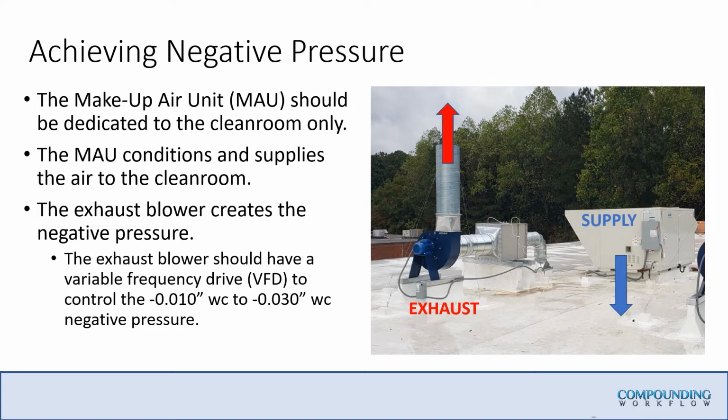I have a current client, and I do a lot of HVAC forensics work. Originally, when the engineer and the architect drew the building 5, 6, 7 years ago, they put one really large makeup air unit to supply the retail area, the break rooms, the office spaces, the clean room, and the non-sterile areas with a bunch of VAV valves. I don't expect you to know what a VAV valve is, but really that's a zone control mechanism, and it's a mess. It's just an incredible, unequivocal mess.